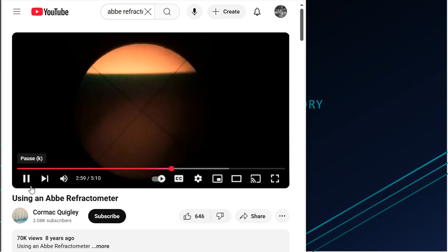And that's controlled using the dispersion control wheel, and you have to adjust that for each different liquid that you measure on the reading. So he's talking about this hazy line that's up here at the top between the light half and the dark half. Very often, depending on what the substance is and your own eyeballs, you might see this area a little hazy or a little fuzzy. And it should be a very crisp division line between them here.